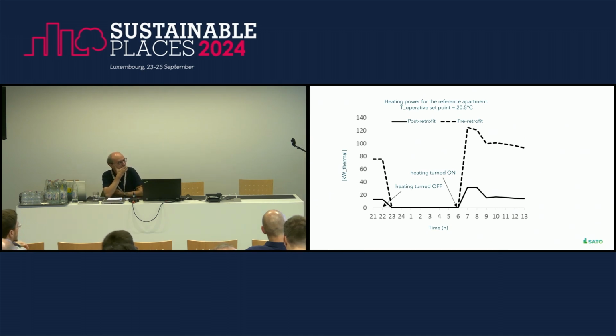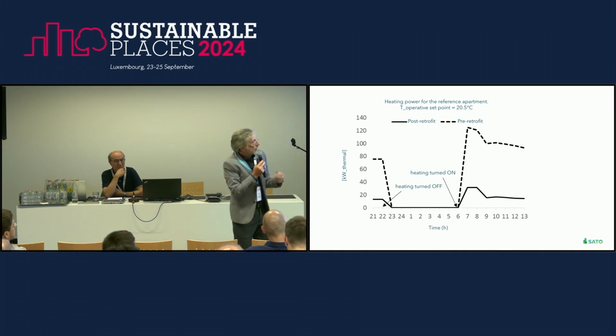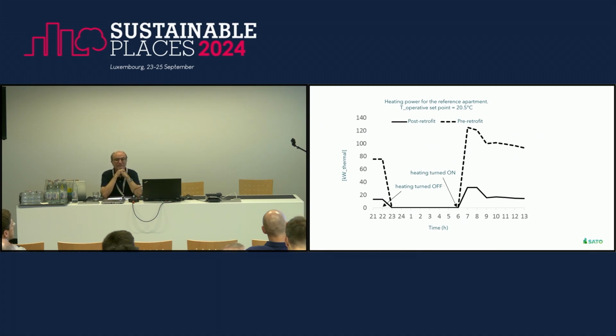And in terms of required power, the pre-retrofit requires, I don't know, 120 kilowatt in the first 2 hours of the morning to be brought relatively rapidly to comfort. After retrofit, we need 30 kilowatt thermal. And you can imagine what that means if you're using a heat pump. The difference on the electric demand is factor 4.